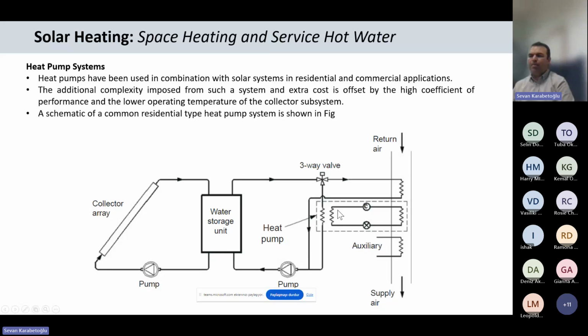In that case, we have a heat pump, also implemented with the collectors, of course, and the main water storage unit is just coupled with the collector and heat pump system. And we have again ducts circulating air. So these heaters warm up the air, and the supply air is warming up the space. Heat pumps are actually better than direct electrical resistance, because COP values are nearly 4 or 5 for the heat pump mode. But for electrical heaters, the COP value is 1, as you know.